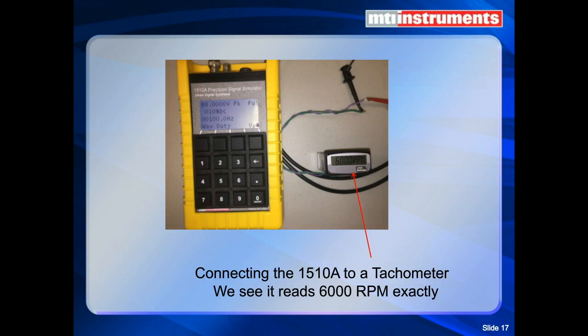It's a little difficult to see in this slide here. We've connected a tachometer up to a 1510. This is a self-powered tachometer, and we see that it's reading 6,000 RPMs exactly. So the time base here is very accurate.